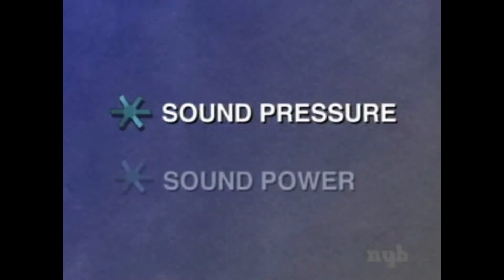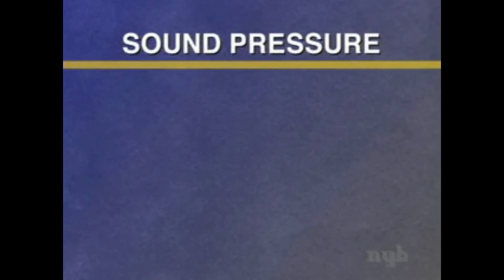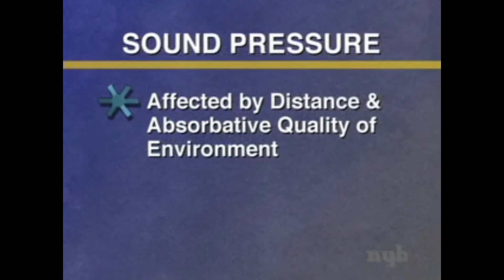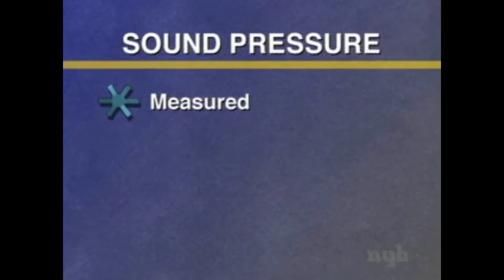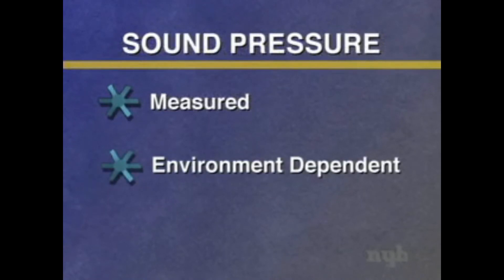In order to measure and work with sound, we use specific terms and units of measure. Two very important terms that are often confused are sound pressure and sound power. Sound pressure is a quantity that is environment dependent. It is affected by distance and the absorptive quality of the environment. It can be measured with a microphone — it's what we hear. It's important to remember that sound pressure is dependent upon the environment.